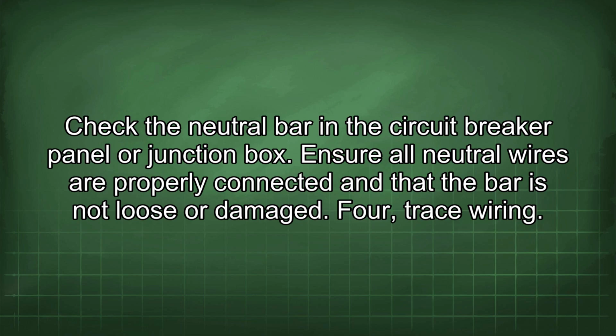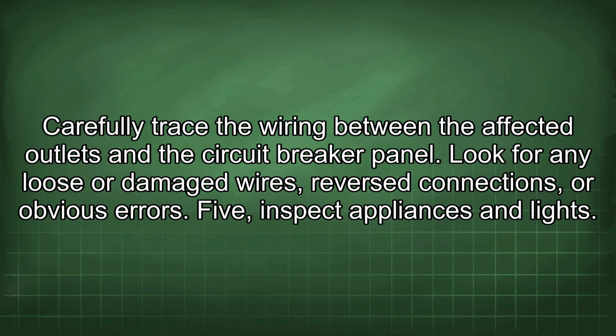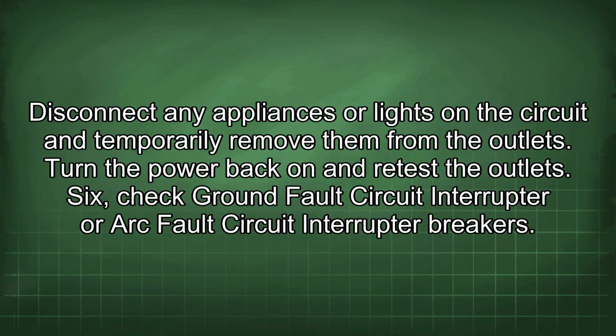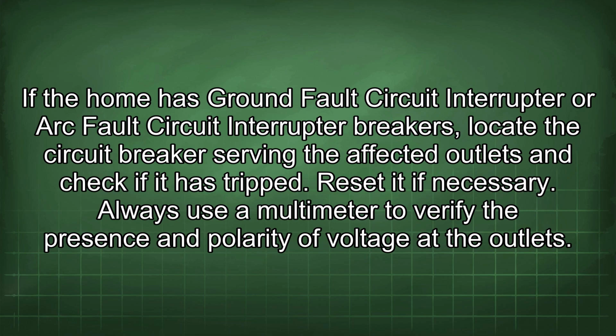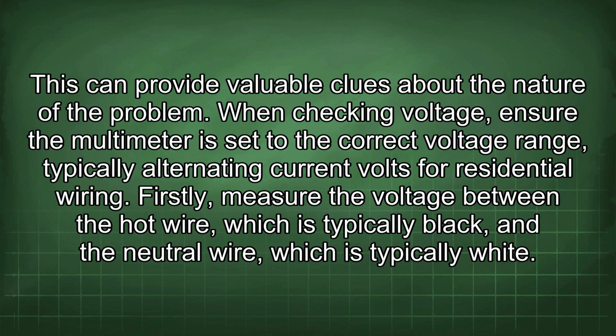4. Trace wiring. Carefully trace the wiring between the affected outlets and the circuit breaker panel. Look for any loose or damaged wires, reverse connections, or obvious errors. 5. Inspect appliances and lights. Disconnect any appliances or lights in the circuit and temporarily remove them from the outlets. Turn the power back on and retest the outlets. 6. Check ground fault circuit interrupter or arc fault circuit interrupter breakers. If the home has ground fault circuit interrupter or arc fault circuit interrupter breakers, locate the circuit breaker serving the affected outlets and check if it has tripped. Reset it if necessary. Always use the multimeter to verify the presence and polarity of voltage at the outlets. This can provide valuable clues about the nature of the problem.